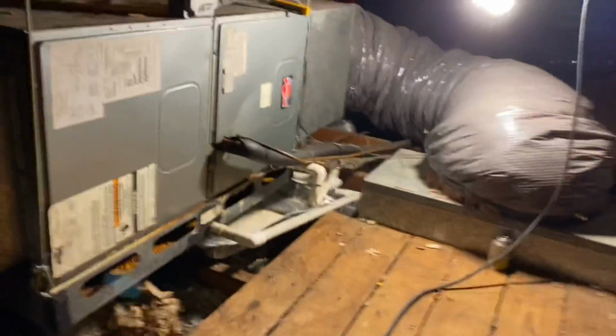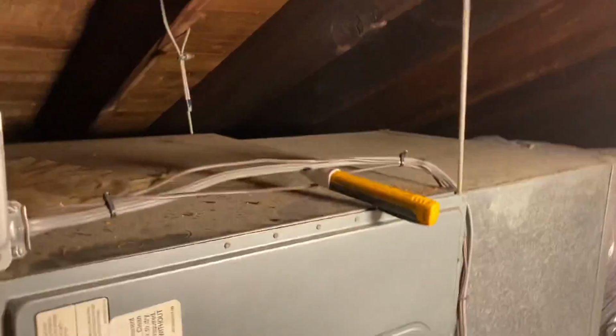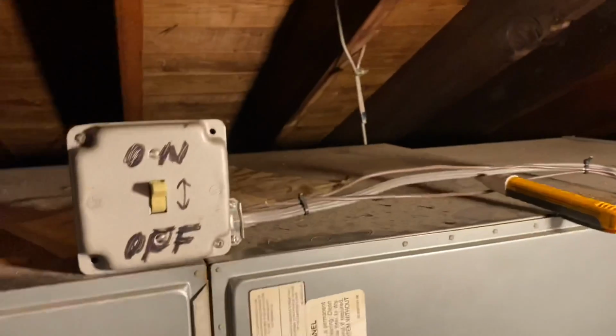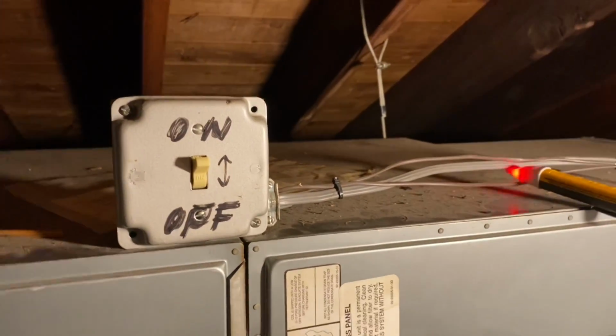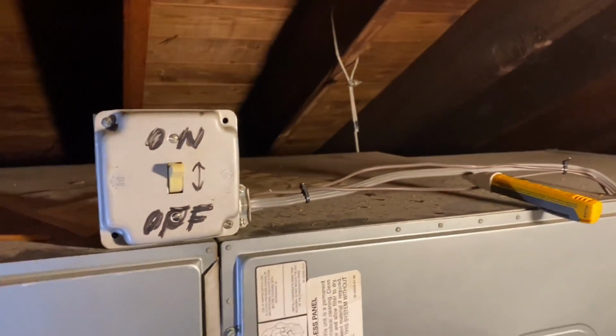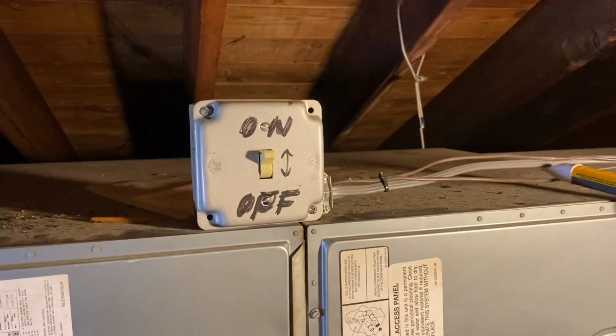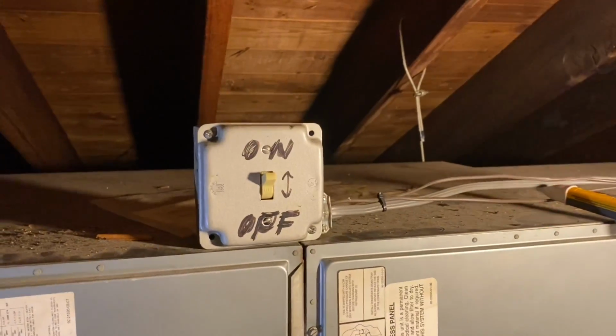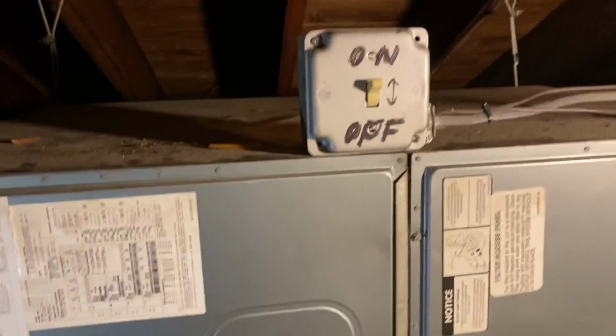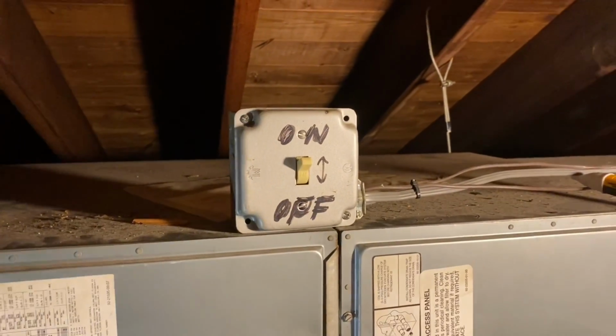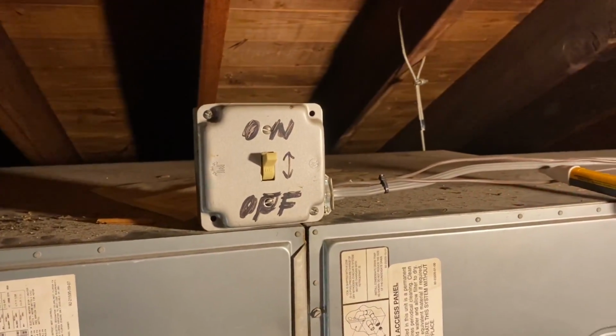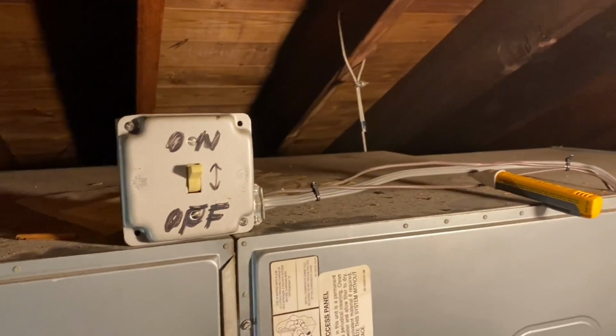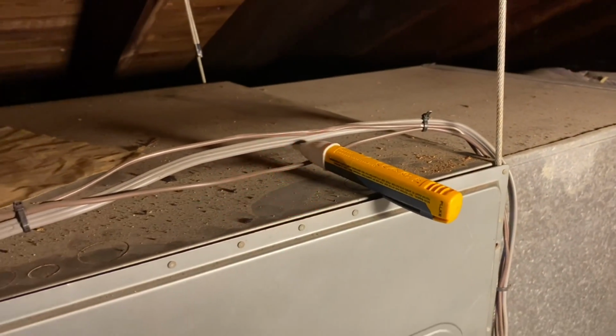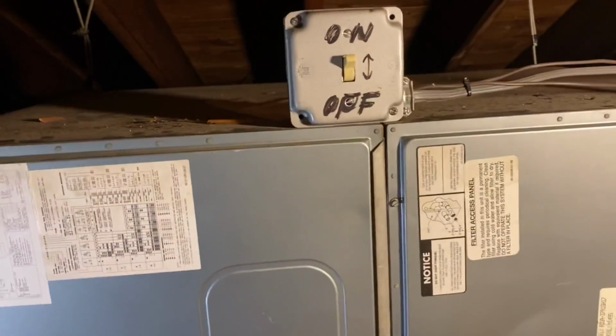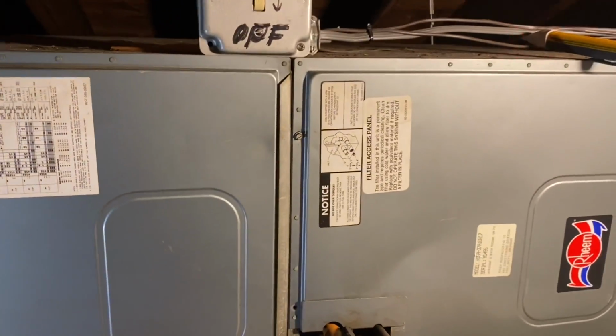All right, Peter, so the first thing we're gonna do is take out our non-contact electrical tester. I had it on the line voltage line. I went down to the circuit breaker panel in the basement. We had a 15 amp double-pole breaker for the AC, which is going to be this, and another 2-pole breaker for the outdoor unit, that was a 30 amp, and both of those are off. Our non-contact tester verifies that. So let's get the drill, 5/16, and let's get the show on the road.